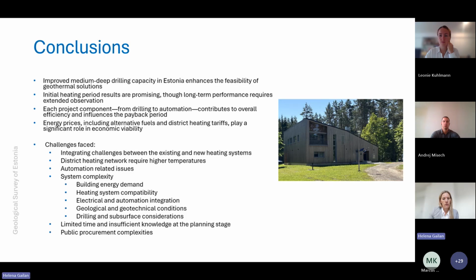I think I already mentioned the challenges we face: integrating two systems, the existing and the new one, has been challenging. In the Roosna-Alliku project, we see that the heating network requires high temperatures, while the ground source heat pump's maximum temperature is like 55 degrees, as the previous heating period showed.